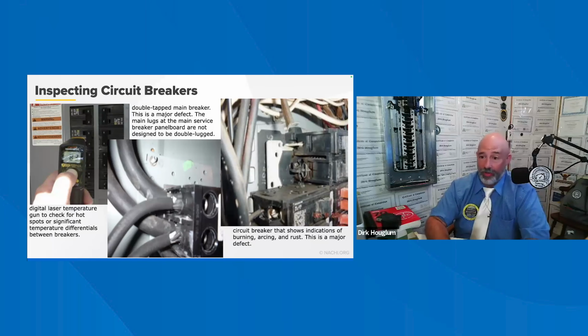Does the breaker have multiple incorrect double taps? Do the 240-volt breakers have the handles tied properly? Do the GFCI breakers work properly? Do the AFCI breakers test and reset properly? Are there any signs of overheating, arcing, or smoke damage on or around those breakers?